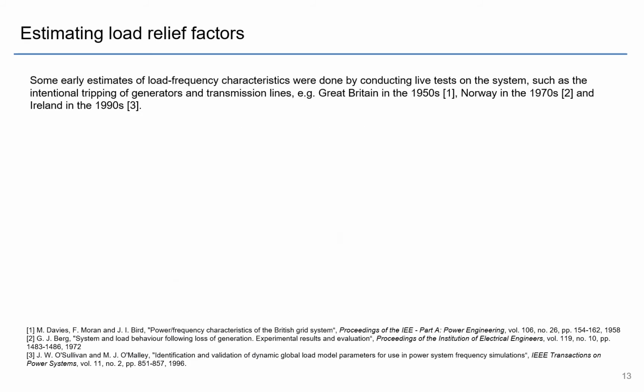Now we want to talk about how we estimate the load relief factor D. Some early estimates of the load frequency characteristics were done by conducting live tests on the system. So this is something we discussed earlier in the conversation about the early SFR models, where when they calculated the power frequency characteristic, they actually intentionally tripped generators and transmission lines. So that study from the 1950s applies here, and as does the Berg study from Norway in the 1970s. There was also a study in the 90s by O'Sullivan and O'Malley, where they also tripped some generators with only one unit for primary frequency control running, and tried to estimate the amount of load relief and load response in the system.